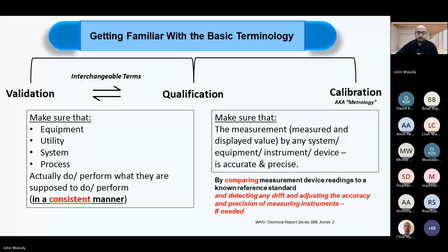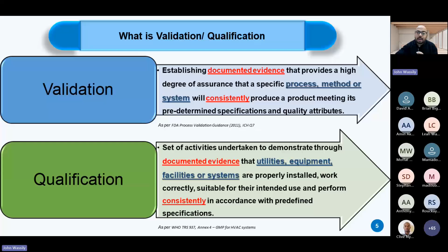Here I want you to differentiate very well between the validation and qualification terms. Yes, they are interchangeable terms, but finally, they share the main concept but they differ in the application. For example, validation is establishing documented evidence that provides a high degree of assurance that the process, method, or system will consistently produce a product meeting its predetermined specs and quality attributes. The qualification term is sharing the main concept, but here it applies on utilities, equipment, and facilities. So we can say finally that validation term applies on the manufacturing process, cleaning process, sterilization process, aseptic process, gowning process, visual inspection process, analytical method, and systems like the computerized systems.